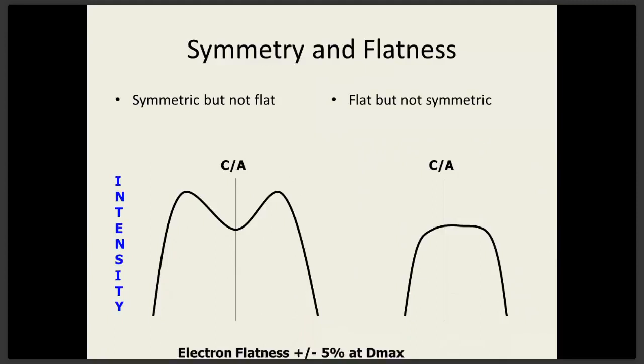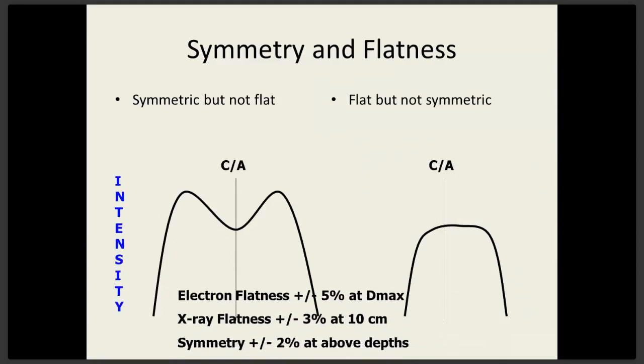Symmetry and flatness, 2 very important concepts for physicists when they're commissioning a machine. The example on the left here shows a beam which is very symmetrical. If you take the area in the left under the curve and compare it to the area in the right under the curve, they're equal. So that is a symmetrical beam. Left equals right. However, Twin Peaks here, very unflat. So this is not a flat beam, but a symmetrical beam.